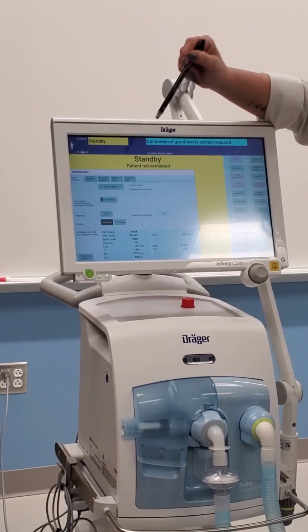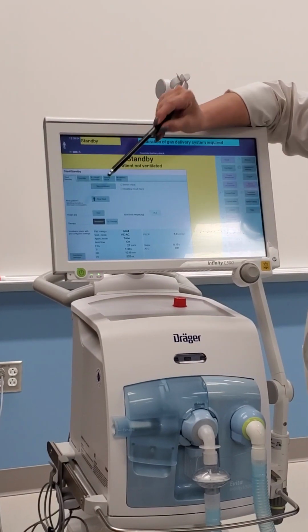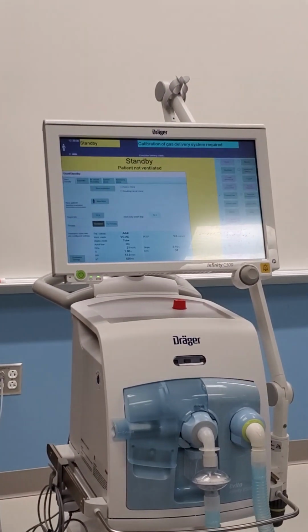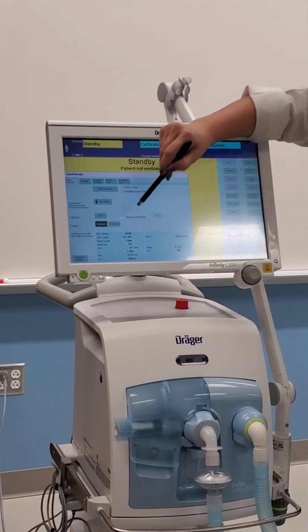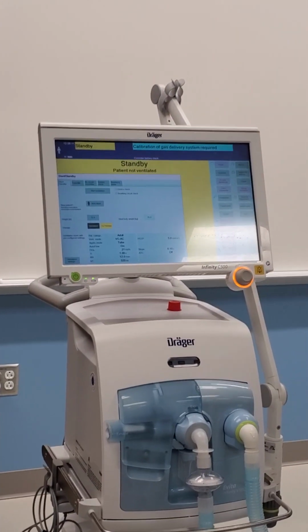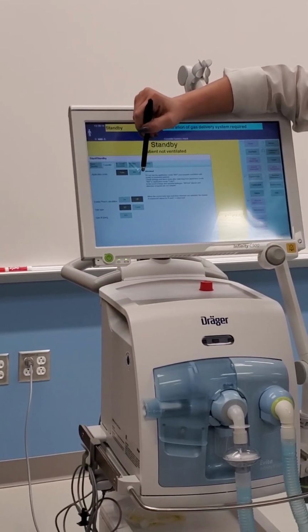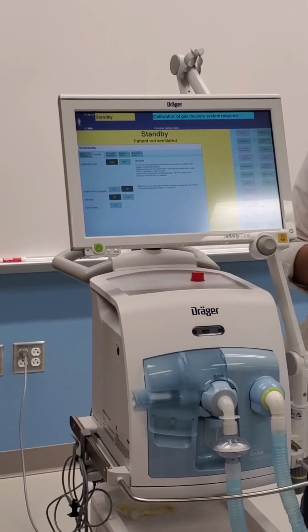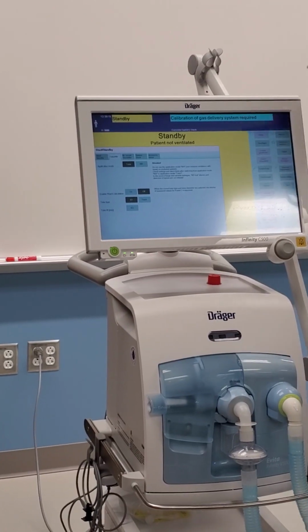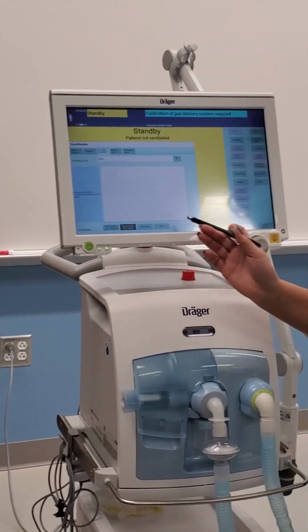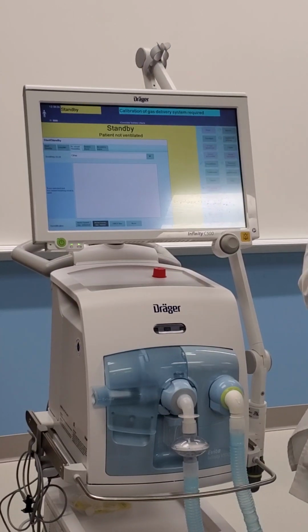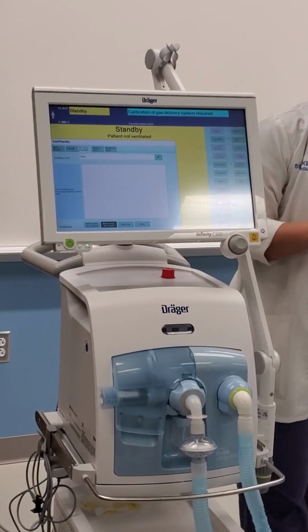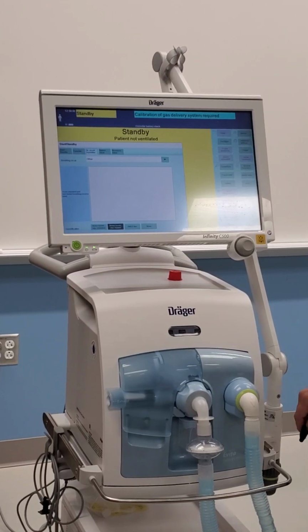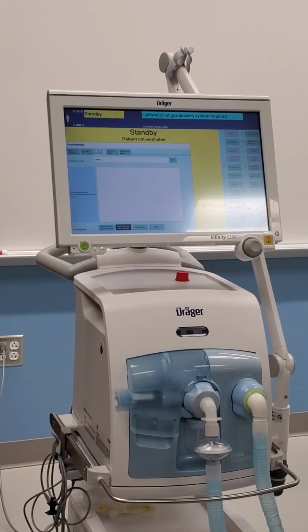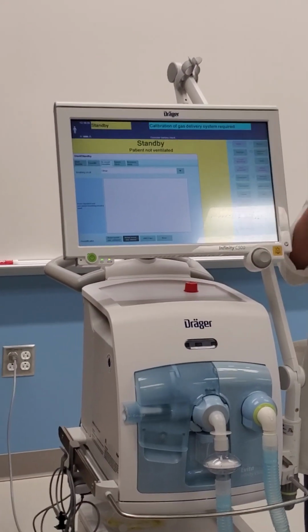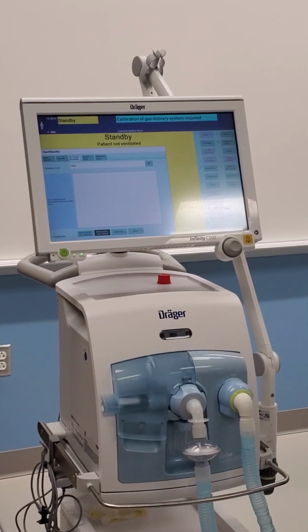So with this ventilator, you can put in the patient's weight here. You can do invasive ventilation. You can do high flow oxygen therapy, which would just be heated inspiratory limb. You can also do non-invasive, where you can run non-invasive ventilation through the ventilator, okay? Humidification, you're gonna choose what type. Is it active, meaning heated with a heated wire circuit? Is it passive, HME? And when you do your SST test, you have to make sure that you're doing it with that selected humidifier. It makes a difference. Make sense?